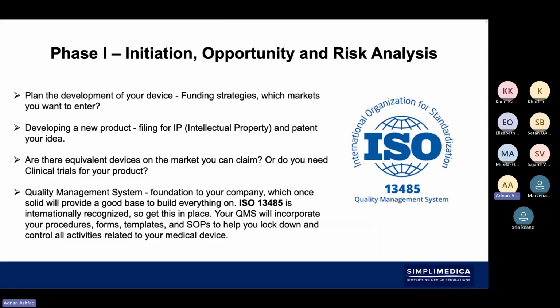So when you get to phase one, it's good to have a quality management system at this point. I mentioned ISO 13485. It's a really good base to have to build upon. If you have a structure in place, which is ultimately procedures, forms and templates, they are your rule book for your device organization of how you will do things. It will allow you to lock down and control your activities also. And that's a really good base to make sure that you're following everything. It's been devised over years. ISO 13485 has been in existence for a very long time.